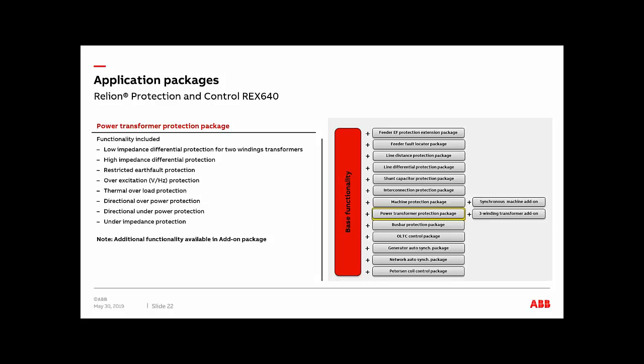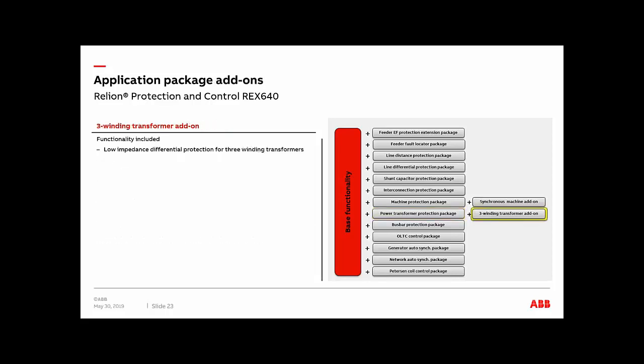That's for your transformer, and it's important to mention that if you only get the transformer package, you will get the 2-winding transformer protection package. You do need an add-on for your 3-winding, and it's going to be exactly the same, but you will get the option of having 3 windings, respective settings for each of the windings, connection groups, vector groups, and you're going to have the same 3 settable slopes for tripping of the differential.